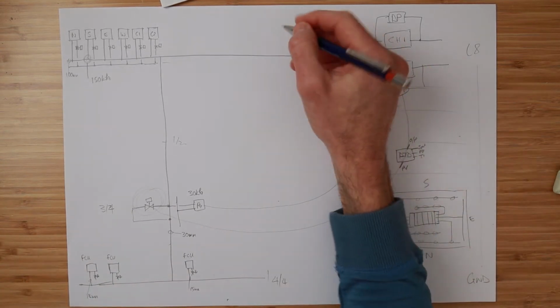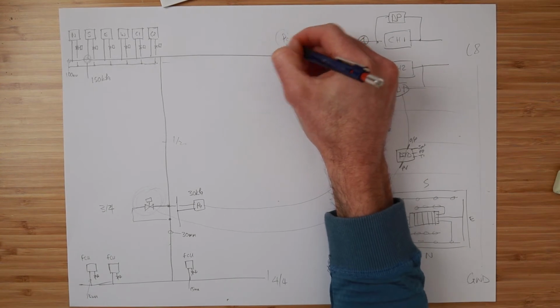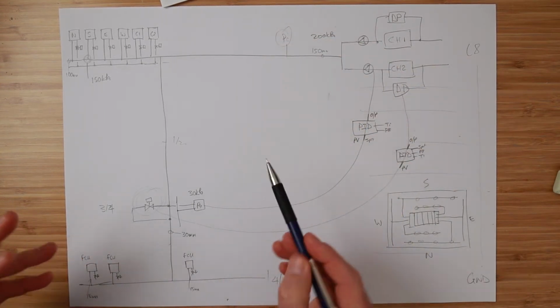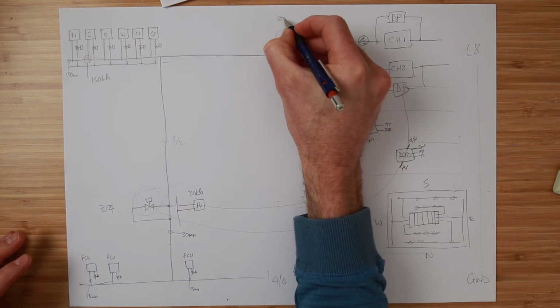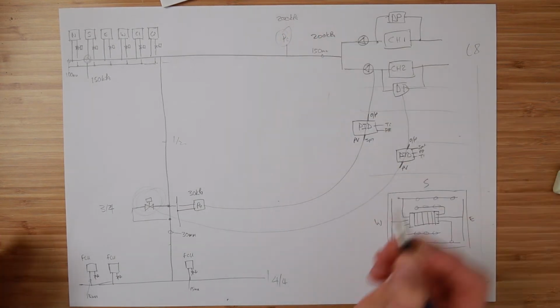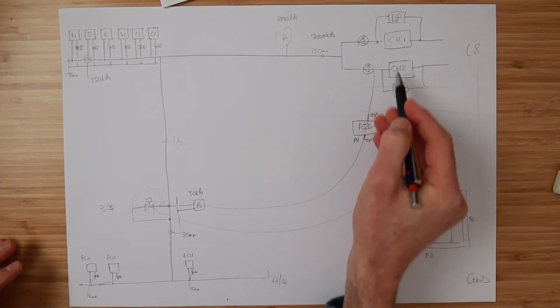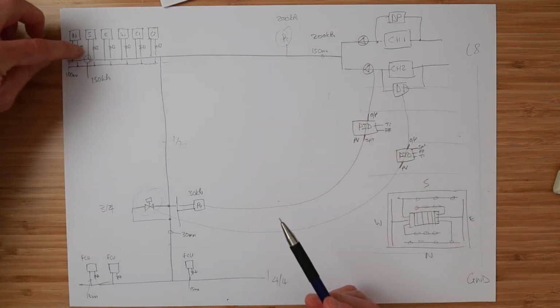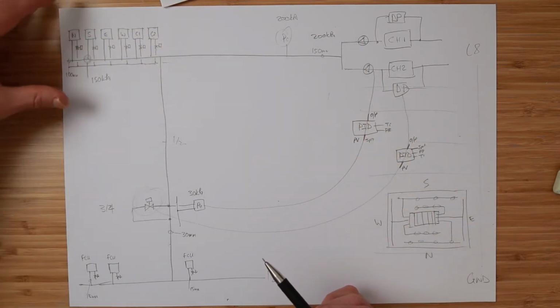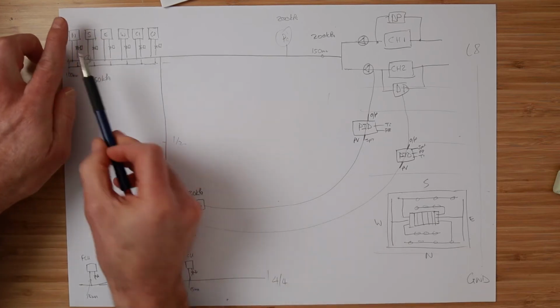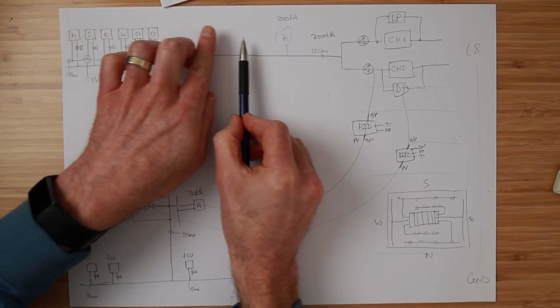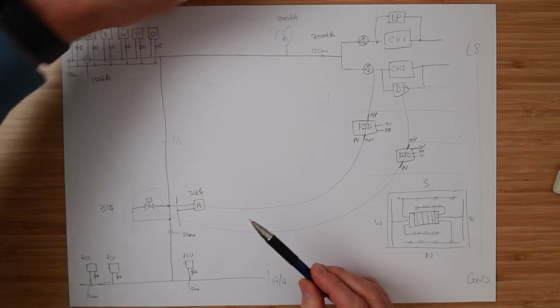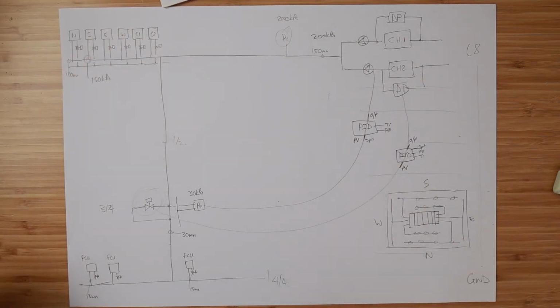The same thing is if you actually install the pressure transmitter up here, it would still work. They would get a set point of 200 kPa from the water balancing guys, and we'd control to that. And as these AHUs start to back off and these two-port valves start to close and the pressure goes up, that increase of pressure here will also result in this pressure also going up and the pump will slow down. So in the most basic terms, you could almost install the pressure transmitter anywhere.